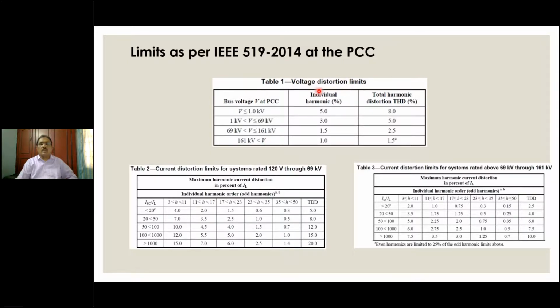So for the voltage distortion, THD voltage, you will find these are the various values. It is 5% for 11 kV if it is total harmonic distortion. Individual order harmonic, that is third or fifth or seventh, we saw that when we talked about basic understanding of harmonics. The third or fifth or seventh individually should be limited to 3%. Total harmonic distortion integration value can be 5%. If it is 110 kV, it will be 1.5 and 2.5. If it is 230 kV, it will be 1 and 1.5. So this is so far as the voltage is concerned.